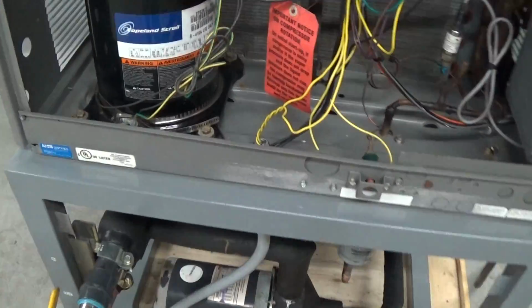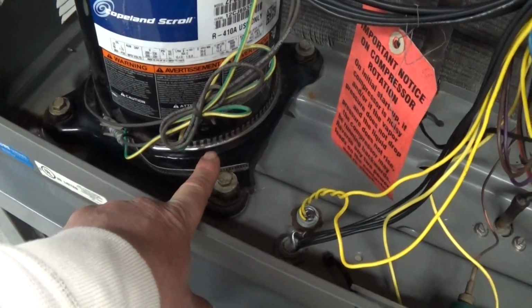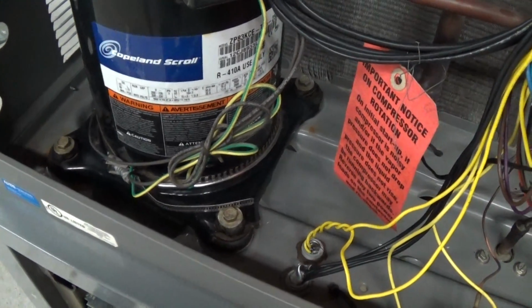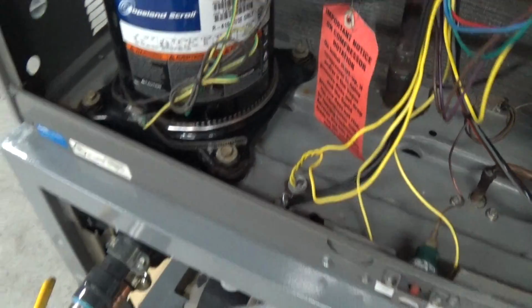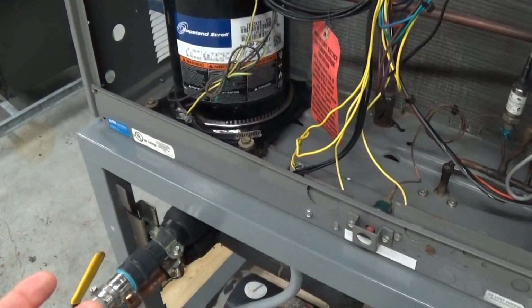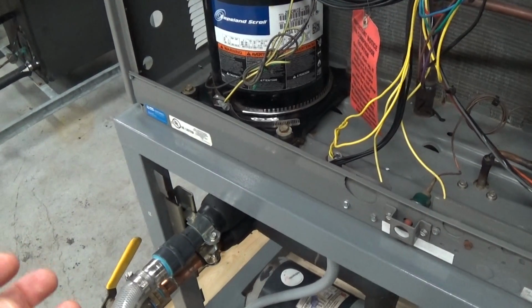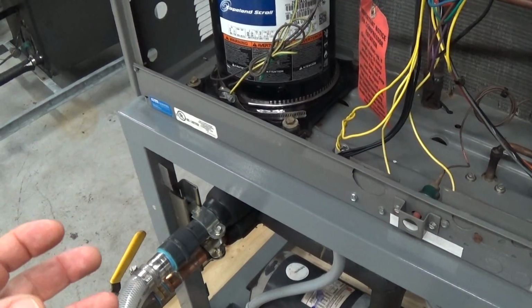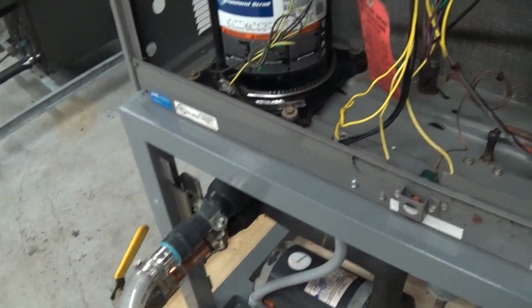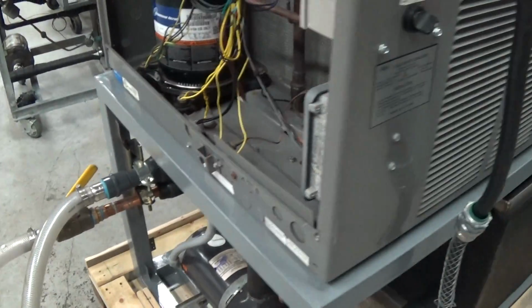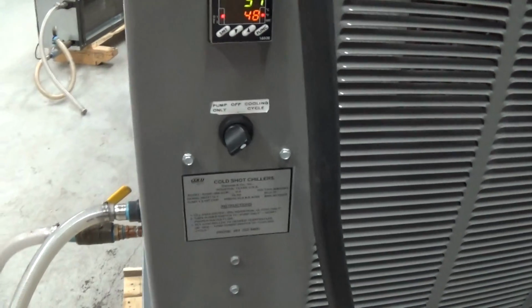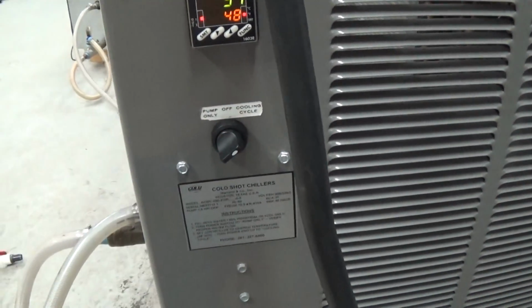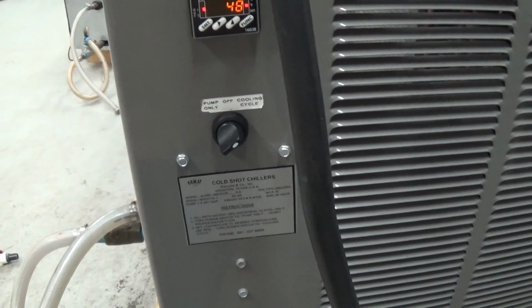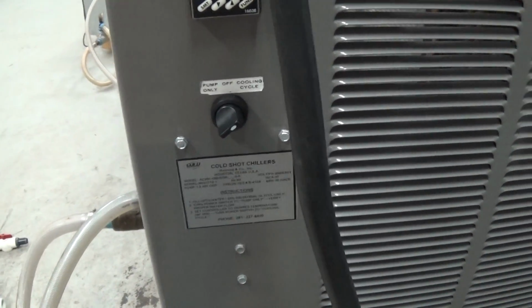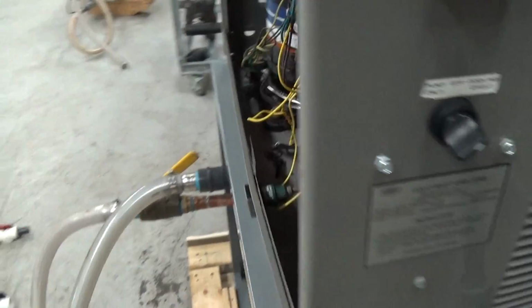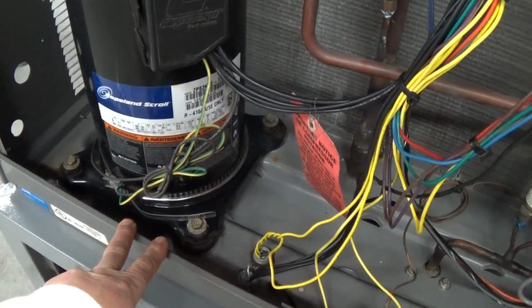survives the journey. This band you see in the compressor, that's what they call a crankcase heater. So even in the winter, yeah, that heater is always on. It keeps the refrigerant warm in there. You never want to get the refrigerant too cold, particularly in an outdoor application. So it's important here that if you want the chiller off, you just turn it off here, especially in the winter. If this chiller is outside in New York, don't disconnect the power at the disconnect on the wall, because that means it's going to get too cold here for a cold startup.